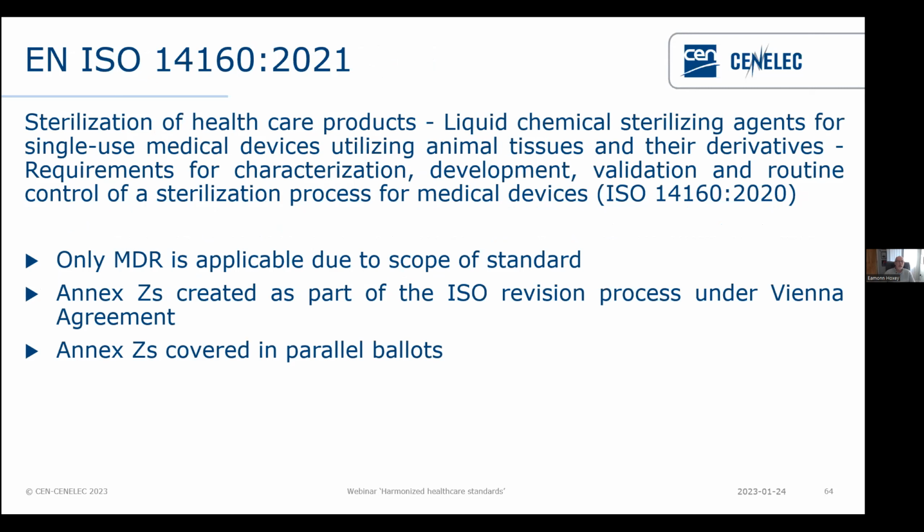That standard deals with the validation and routine control of liquid chemical sterilizing agents that are used for single-use devices containing animal tissues and their derivatives. In this case, the scope of the standard is only products that are medical devices, so only the MDR was applicable to the scope of the standard.